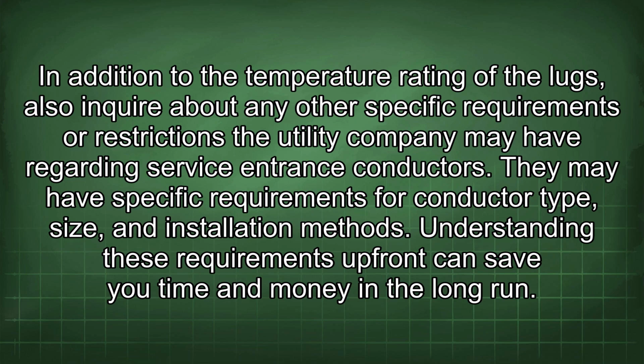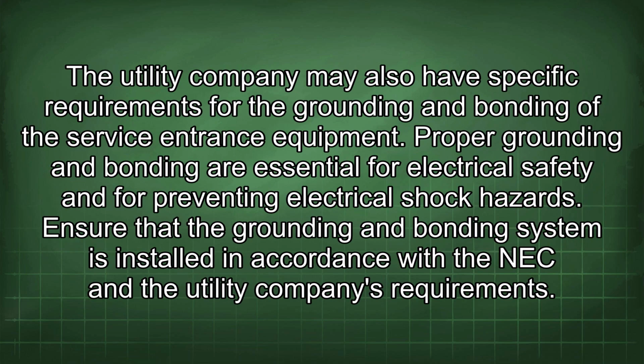In addition to the temperature rating of the lugs, also inquire about any other specific requirements or restrictions the utility company may have regarding service entrance conductors. They may have specific requirements for conductor type, size, and installation method. Understanding these requirements upfront can save you time and money in the long run. The utility company may also have specific requirements for the grounding and bonding of the service entrance equipment. Proper grounding and bonding are essential for electrical safety and for preventing electrical shock hazards. Ensure that the grounding and bonding system is installed in accordance with the NEC and the utility company's requirements.